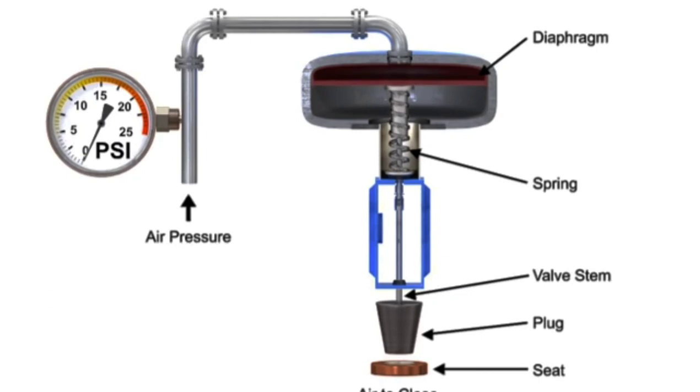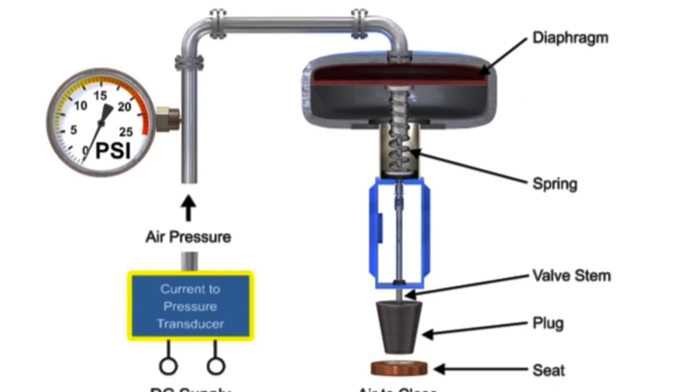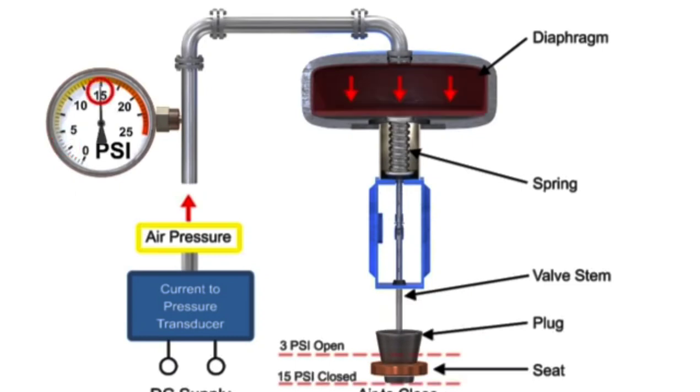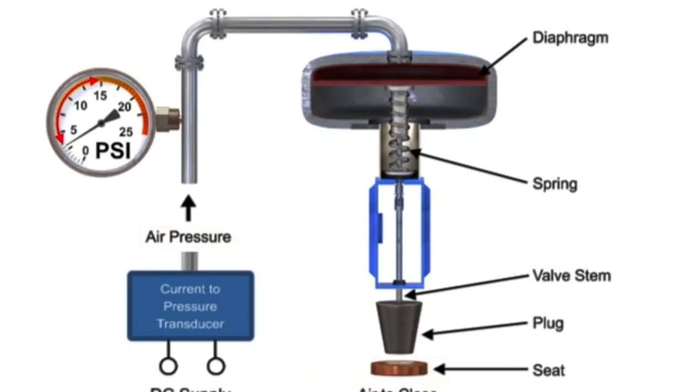To vary the position of the restrictor and flow through the valve, a current to pressure transducer can be used to provide a 3 to 15 PSI signal to the diaphragm. At 3 PSI, the valve is maintained open and at 15 PSI, the valve is maintained closed. Pressures between the 3 to 15 PSI range proportionally change the flow of the valve.